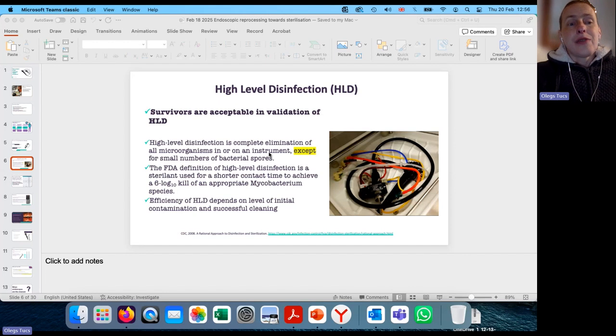So that is not something you would use in validation, of course. Now, there are criteria, there are standards for a process or a chemical to be classified as a disinfectant. For example, the FDA, Food and Drug Administration in the States, defines high-level disinfection as a sterilant used for a shorter contact time to achieve a 6-log kill of appropriate mycobacterium species. So, high-level disinfection to some level is comparable with sterilization. Bring down the number of mycobacteria 1,000,000 times. Kind of sounds familiar to sterility assurance level, doesn't it?